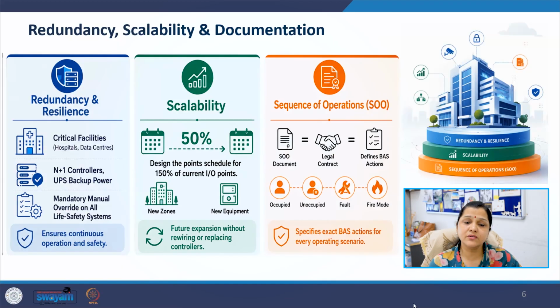Now let us discuss documentation. One of the most important BAS documents is the sequence of operations or SOO. This document explains exactly how the system should behave in every operating condition. For example, what should happen during occupied mode, unoccupied mode, fire condition, or equipment failure. The SOO acts as both a technical reference and a contractual document. If the SOO is unclear, commissioning problems usually appear later.